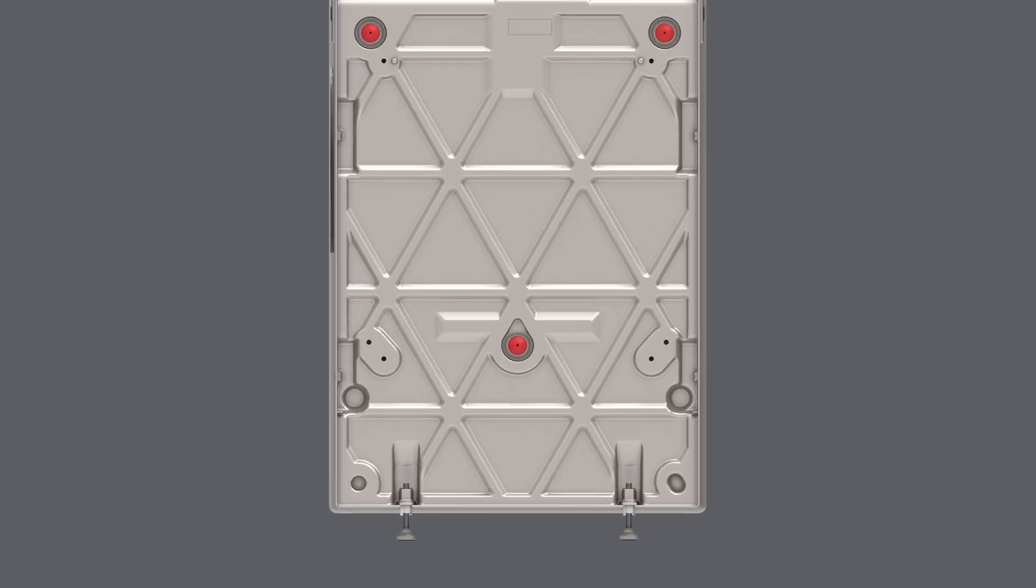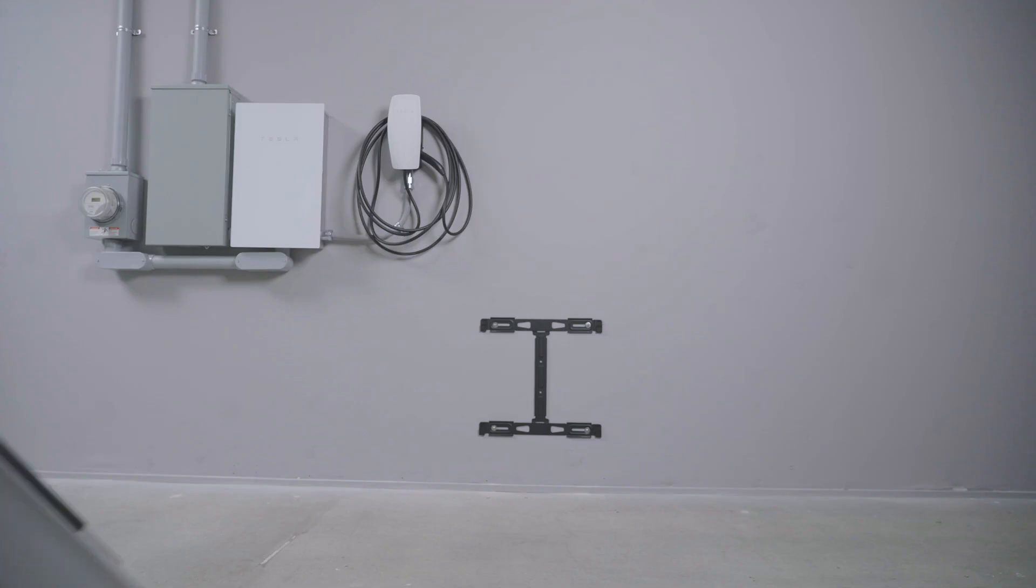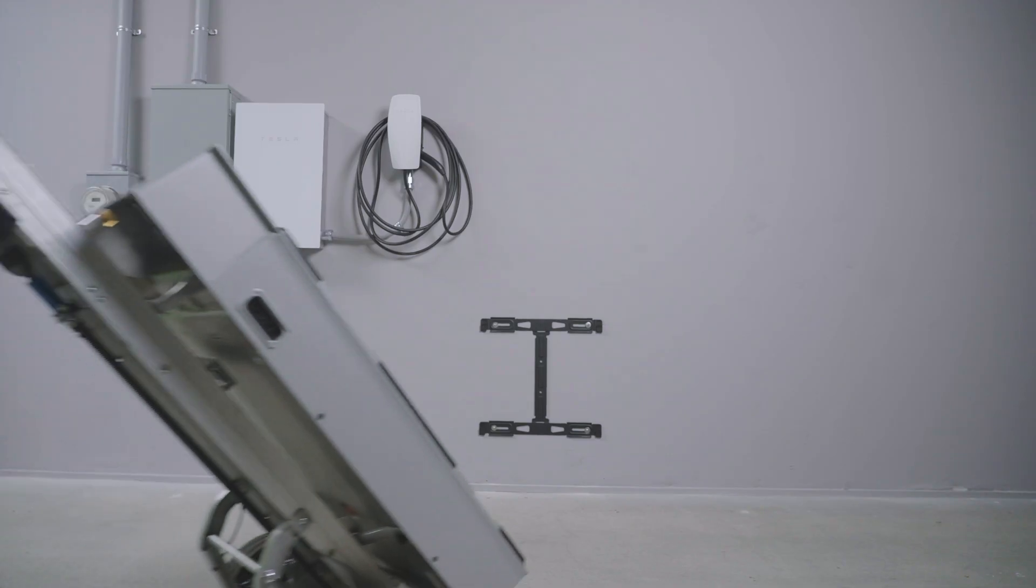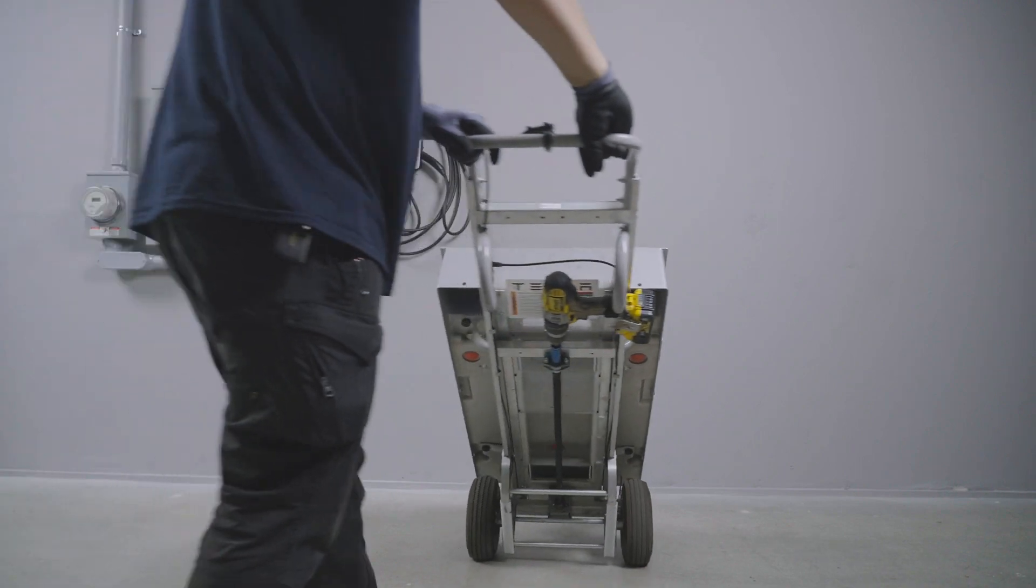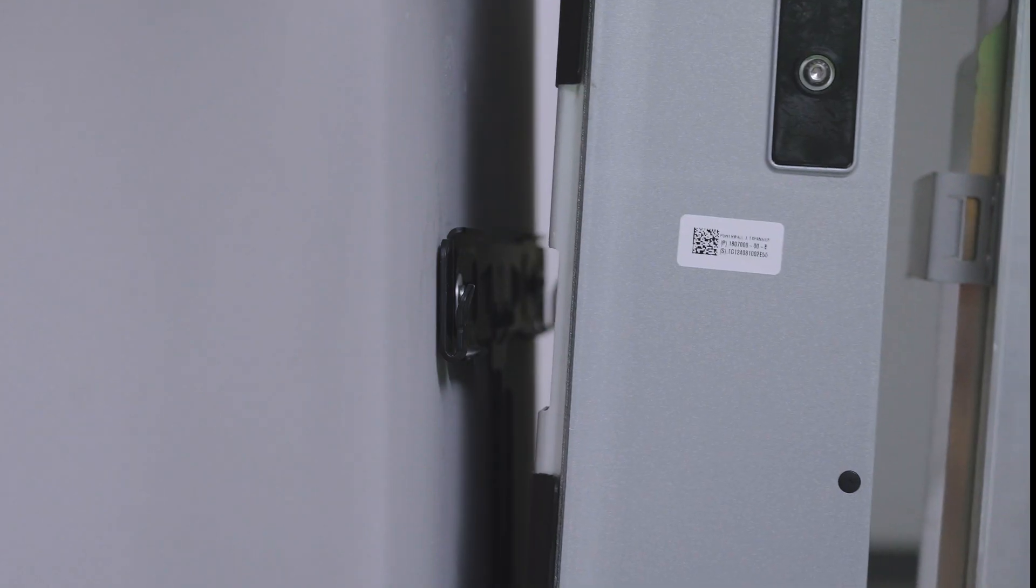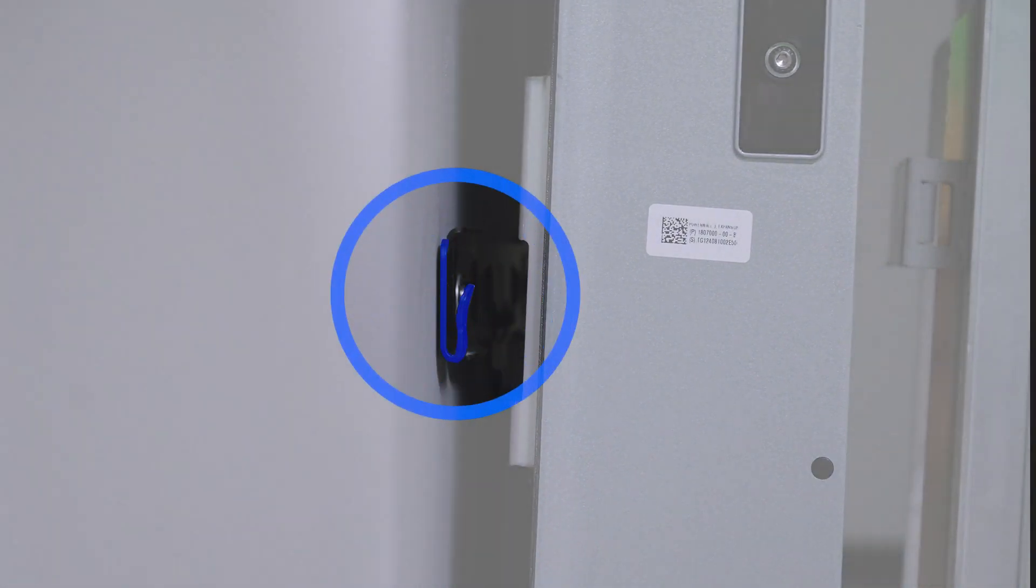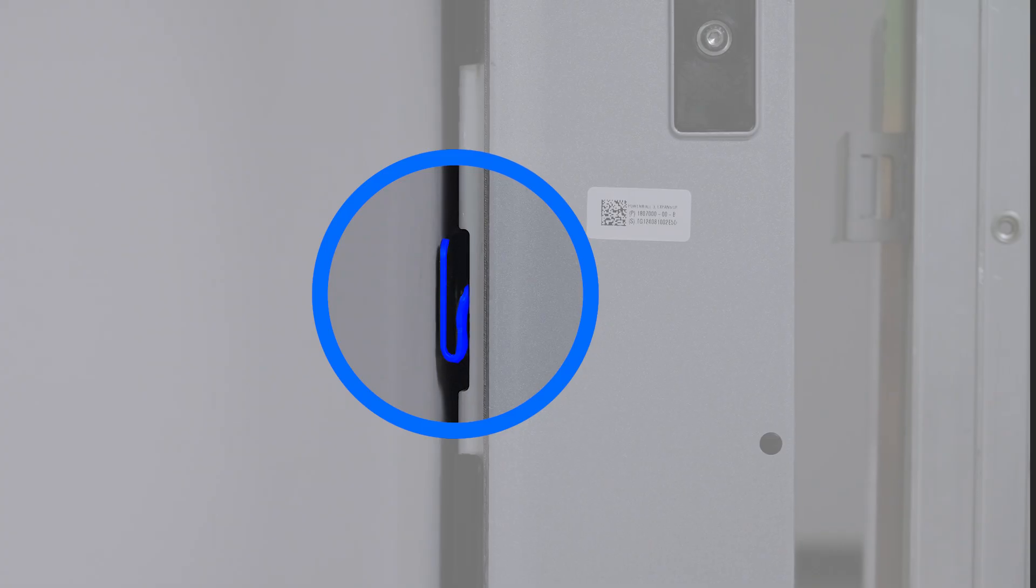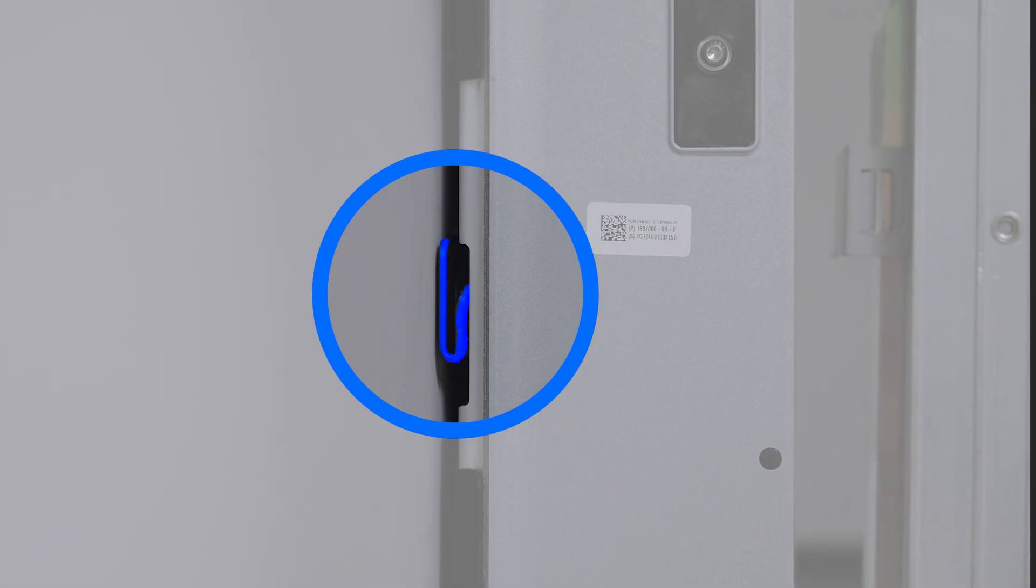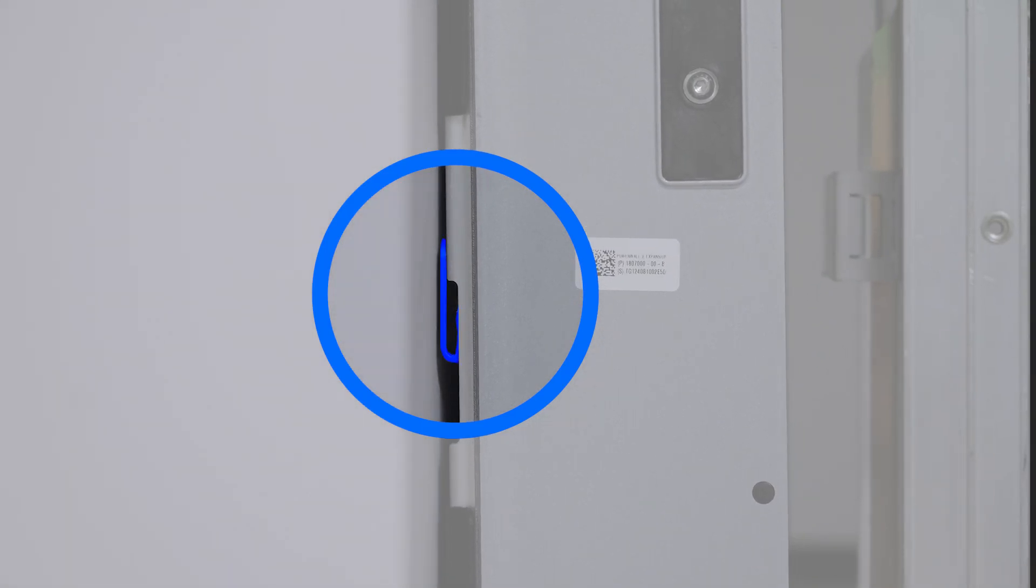For the unit mounted to the wall, ensure that the leveling feet start all the way up. Use Powerwall dolly to position the Powerwall 3 expansion so the mounting cleats are just above the flanges on the bracket. Lower the unit until both the upper and lower sets of cleats engage the flanges on the bracket.